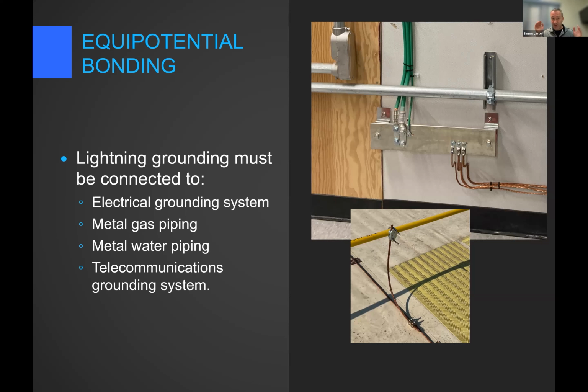Yes, we have to maintain 2 meters separation between our grounding and an electrical ground, or a gas pipe, or a buried oil tank or something like that. But as long as we maintain that separation, we do still have to be connected up to that. So all of those different electrical systems and the metal gas piping, metal water piping, all has to be connected up with our lightning protection system.